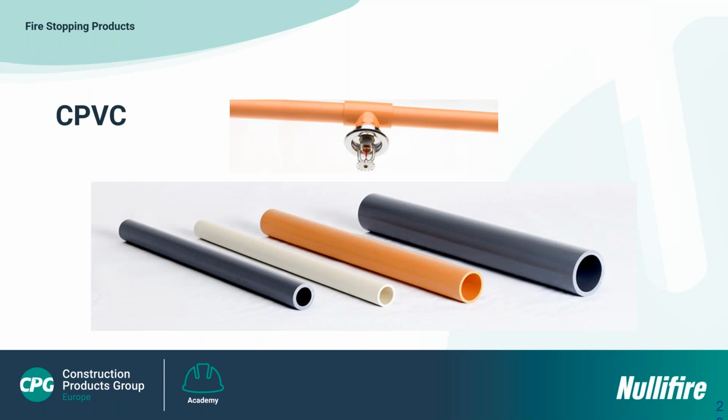So, CPVC. All CPVC plastic parts require a closing device, like a strap, HP mastic, or for us, HP blue mastic. And we must be on a manufacturer approved list. We are on one of them, the Lubrizol one. We're not currently on the Spears one. If you speak to our technical team, they would be able to advise what we would recommend. But the main ones tend to be, in the UK, Lubrizol or Spears. They're highly reactive products, the CPVC pipes, and multiple precautions have to be taken when installing them.